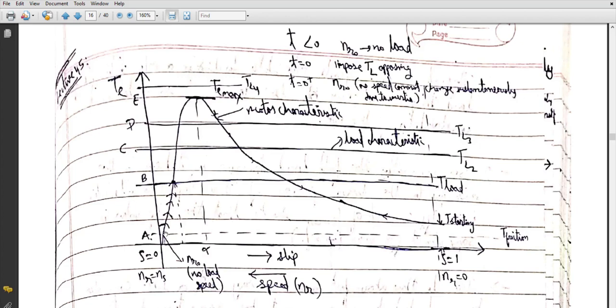The maximum capacity is when TL equals TE_max. But in practice we don't do that. The maximum full load torque applied to an induction motor is generally taken to be around 0.5 times TE_max — half of the maximum torque available. This is because if load TL3 is applied and the rotor overshoots past the maximum torque point due to inertia, the machine will stop. So full load is kept at about half of TE_max.